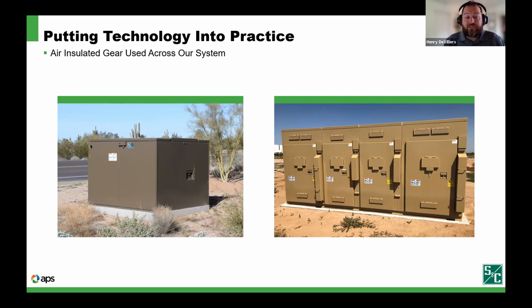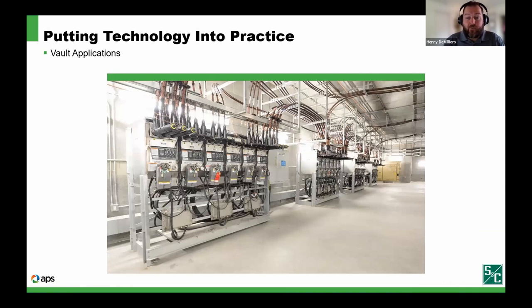We also use gas insulated switchgear in our networks and vaults and in places where we have to build next to lakes and rivers and things like that, just because of that added insulation and knowing that we're going to keep moisture and everything out. With our experience in using the gas insulated switchgear, we have realized the benefits of using that in our pad mounted applications as well. So we have started using gas insulated pad mounted switchgear in places where we maybe don't have the real estate available to put multiple four bay switching cabinets. And because of the gas insulation, we can squeeze six switches into a much smaller footprint.